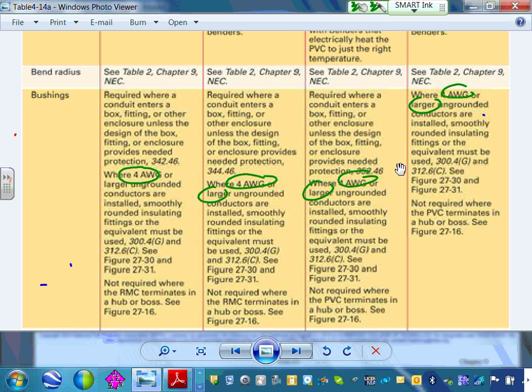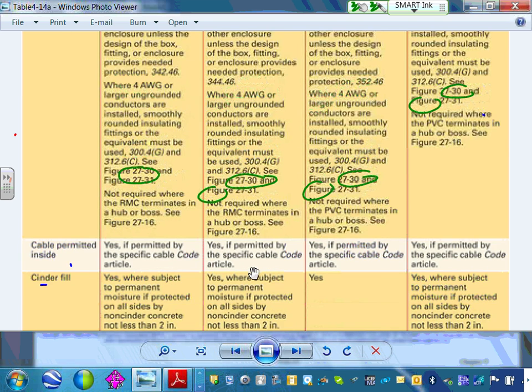If the conduit is threaded, like rigid, it's required on every side. So when you bring it into a threaded rigid, you have threaded fittings, guys, right here, and when you pull a conductor, what's going to happen to these conductors when they touch the place where you threaded? It's going to damage them. So for threaded conduits, they always put bushings, any conduit, regardless of the size. All other conduits only if number 4 or larger. Okay. So that's probably when you do the installation.